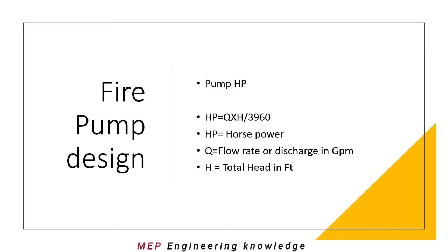The formula for horsepower is: HP = Q × H / 3960, where HP is horsepower, Q is the flow rate or discharge in GPM, and H is the total head in feet. So whichever values we have in meters, the total head needs to be converted into feet to arrive at the HP.